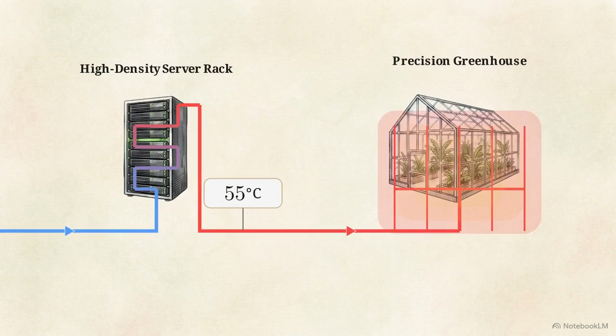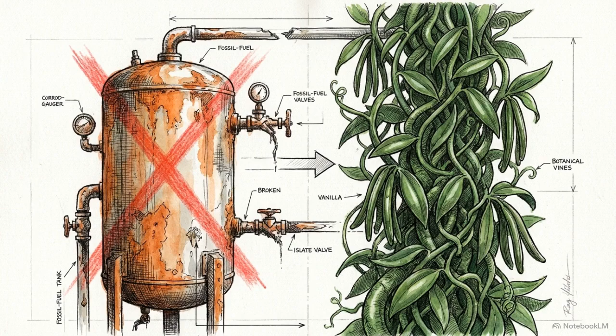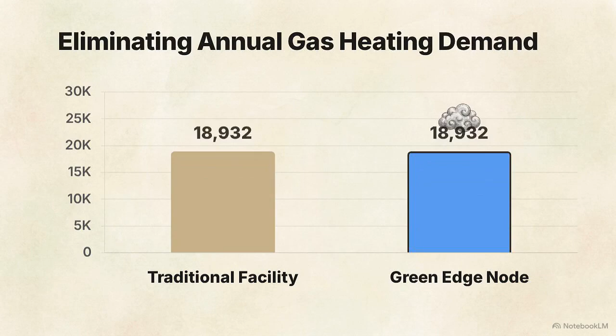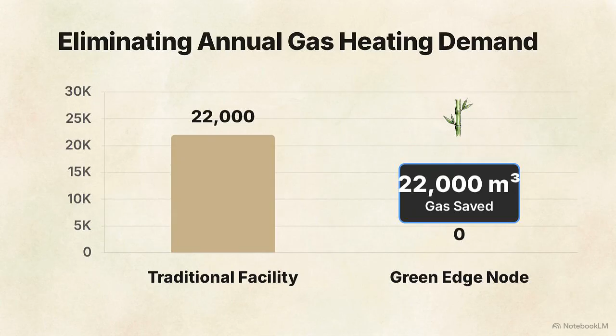Vanilla is an exceptionally high-value crop that demands highly stable, elevated temperatures and high humidity. These precise agricultural requirements perfectly match the continuous thermal output of the GPU cluster. By acting as the thermal sink for the data center, the greenhouse entirely eliminates its need for traditional fossil fuel-based heating systems. This two-way energy sharing saves an estimated 22,000 cubic meters of gas per unit every single year.